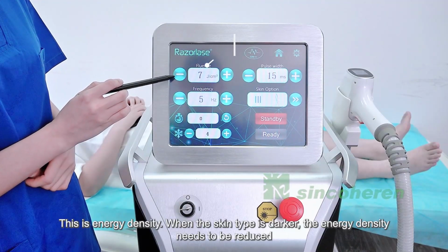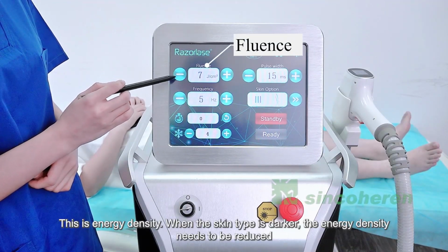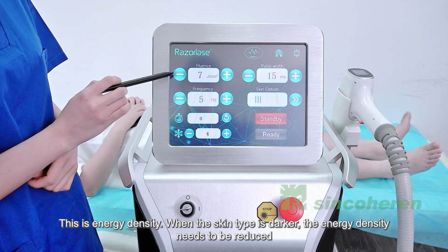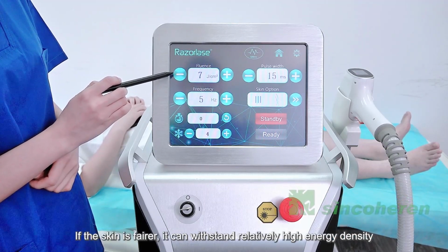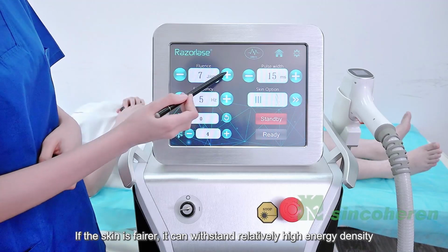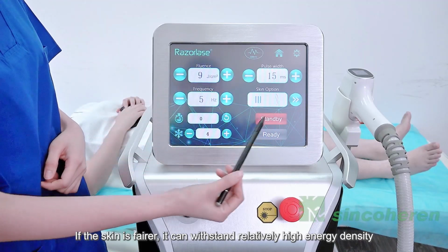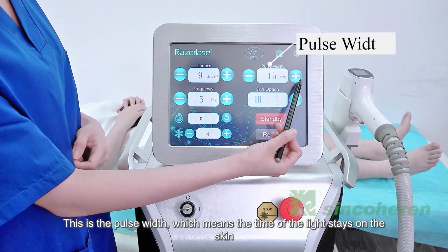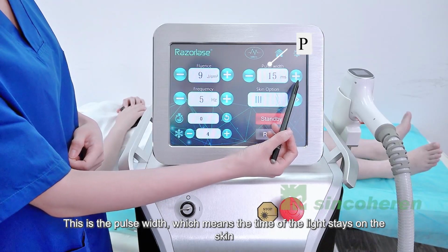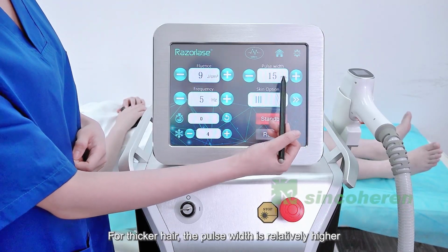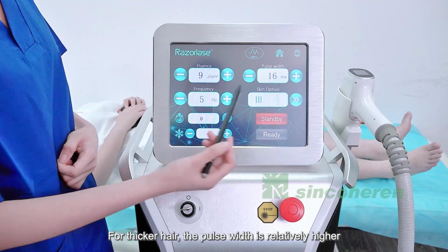This is energy density. When the skin type is darker, the energy density needs to be reduced. If the skin is fairer, it can withstand relatively high energy density. This is the pulse width, which means the time the light stays on the skin. For thicker hair, the pulse width is relatively higher.